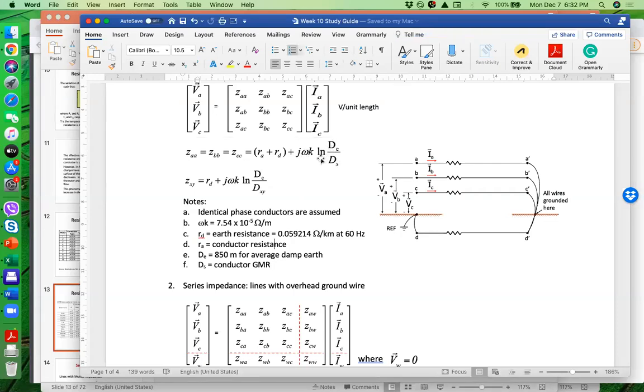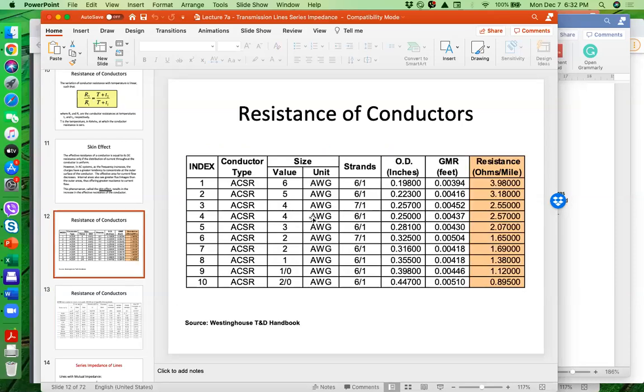DE = 850 meters for average damp earth. If the cable is above water, DE ranges from 8.5 to 85 meters. If above dry earth, use 2688 meters. Above swampy ground, use 269 to 850 meters. By default we use 850 meters. DS is the GMR of the conductor from the spec sheet. If only the diameter is given, the GMR equals the radius multiplied by e to the negative one-fourth.